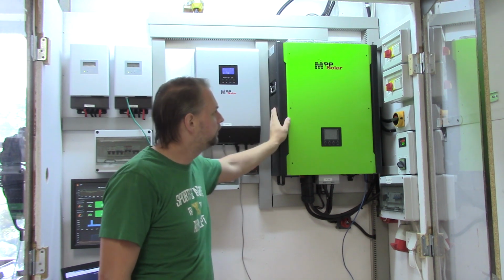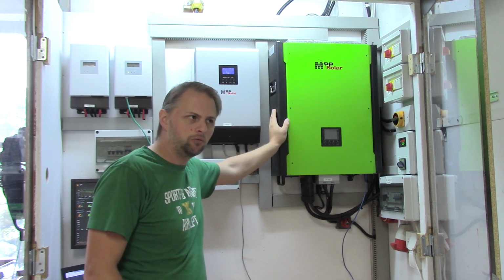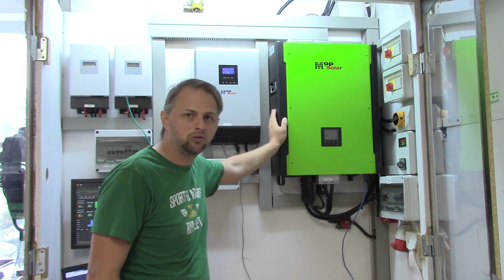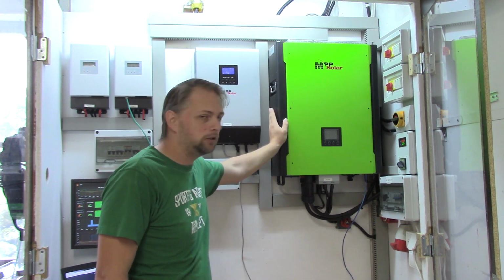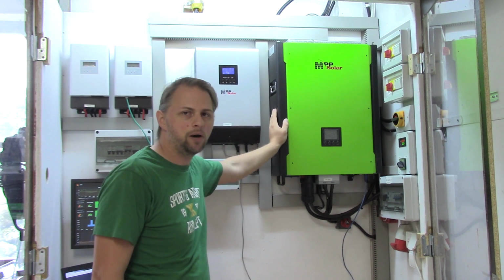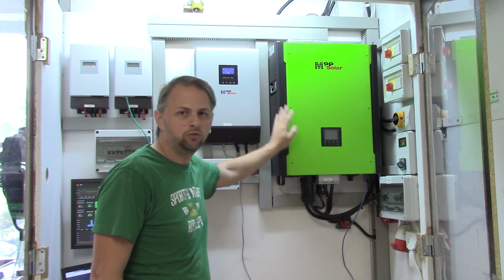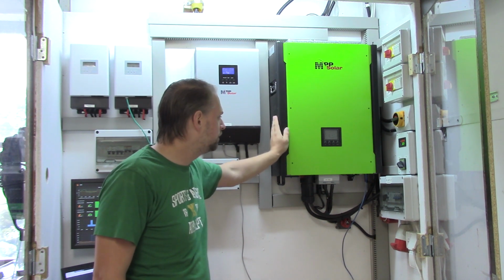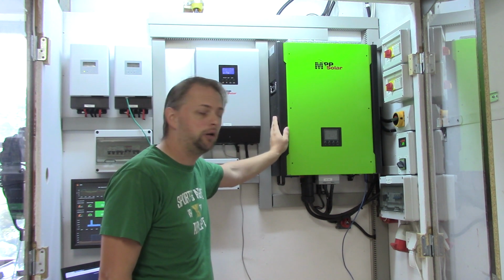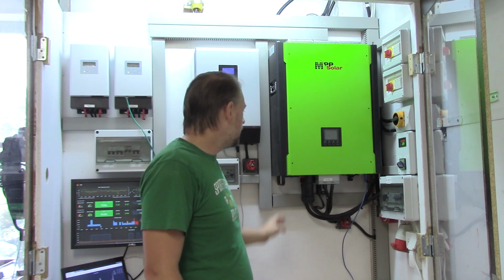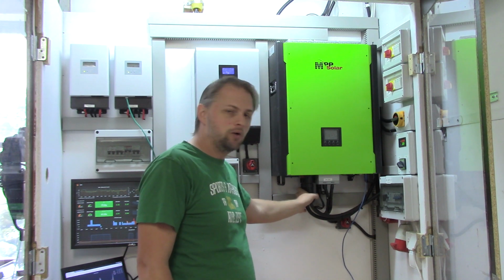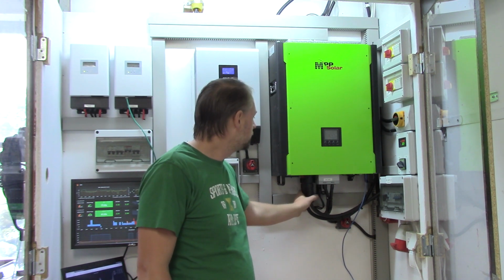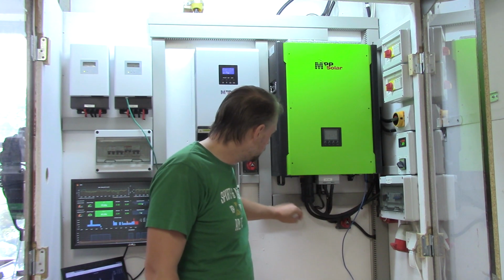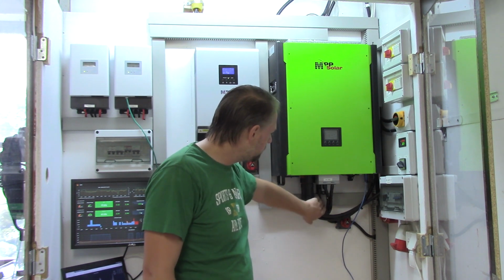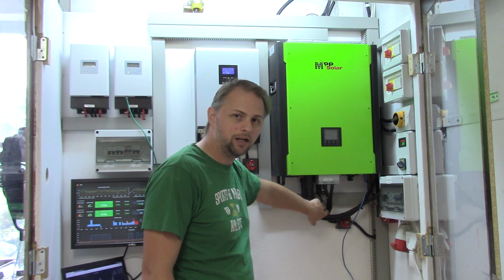It's not the most efficient machine because it draws somewhere around 200-300 watt idle, and that's quite a lot unless you are using a lot of power. So for those that aren't using anything during the night, this may not be sufficient, but for me it works really good. It has incoming and outgoing AC on this side here, and the battery is tied in here and goes down to the junction as well, and the same goes with the PV that you can see inside here.